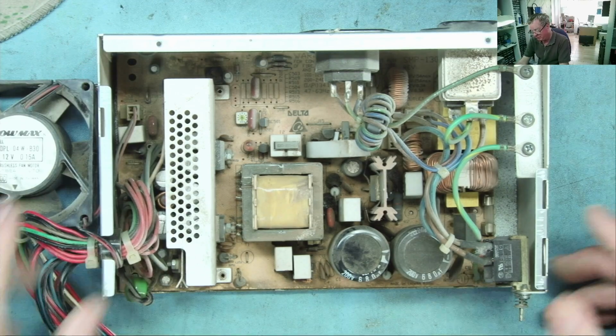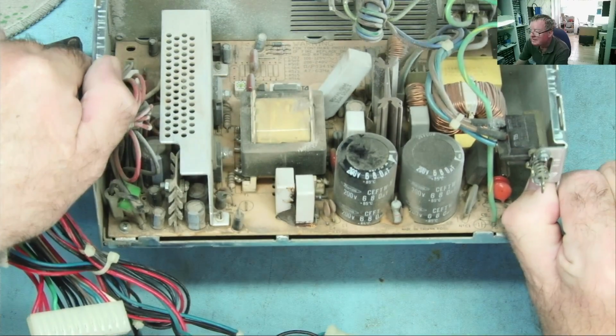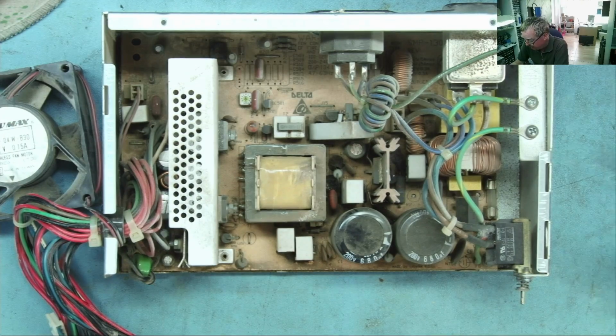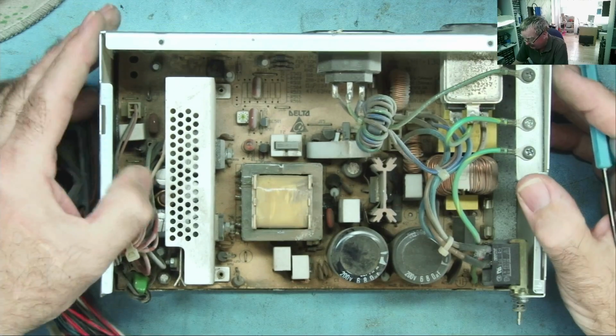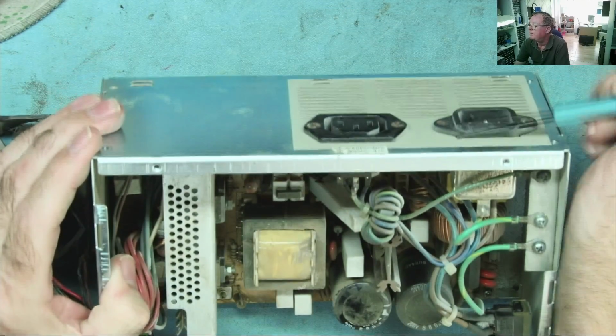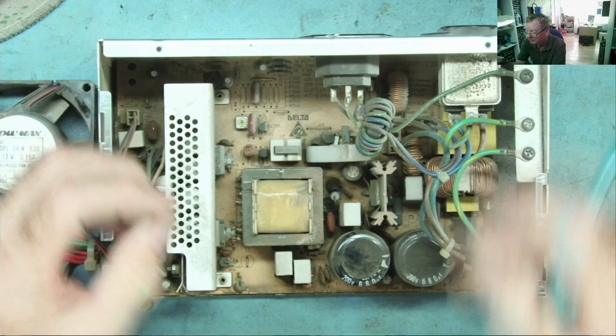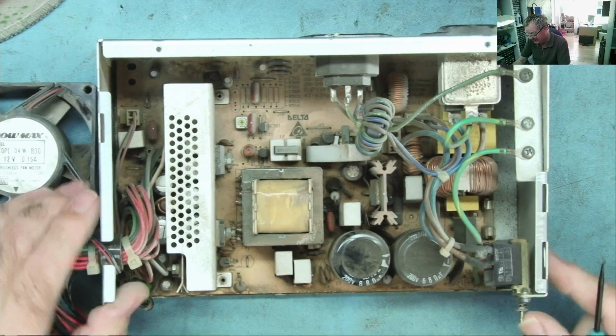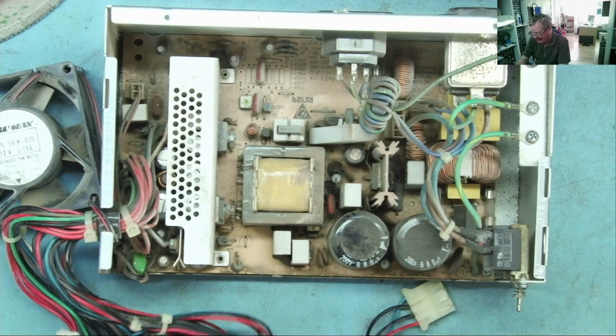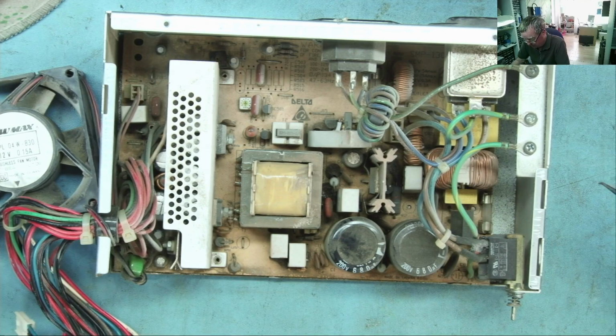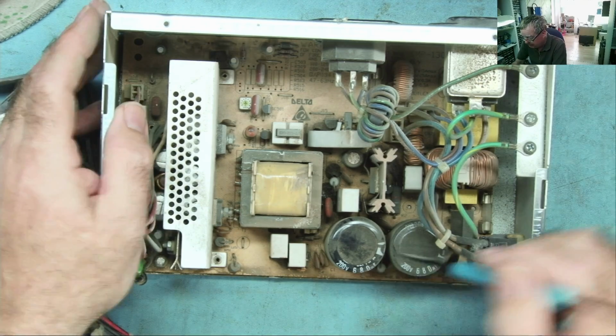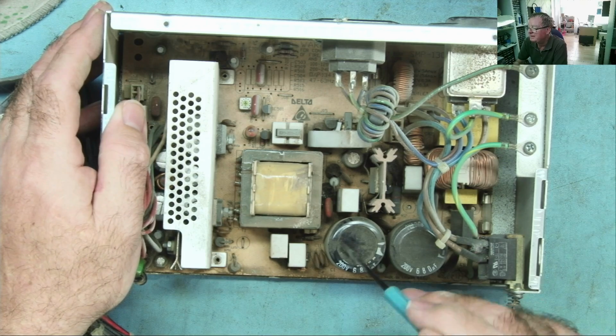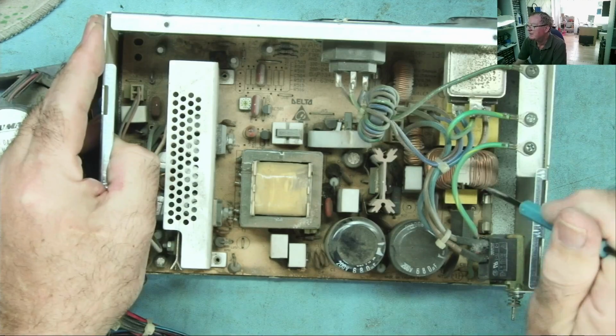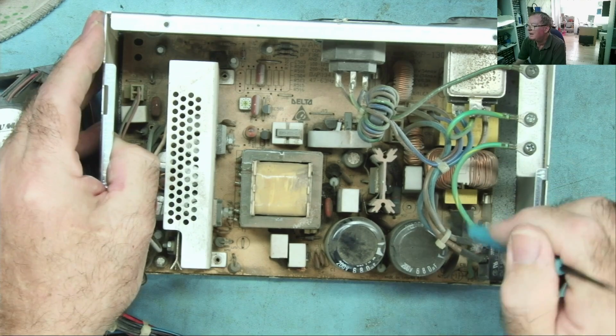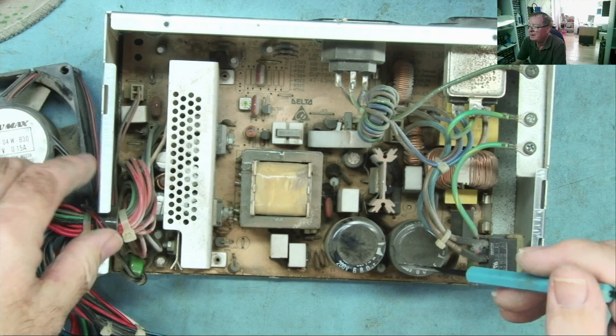But I'm sure you will agree it'd be much nicer to try and fix this. The fault with this: when I tried it, I connected a power lead from my current limiting light bulb. The light bulb came bright and then went dimmer. So the capacitors inside here definitely charged up, power got into it, but it didn't start, it didn't work. Because I know power got as far as these capacitors, we can say the fuse is okay, or the input wiring is okay - the fault is somewhere else.